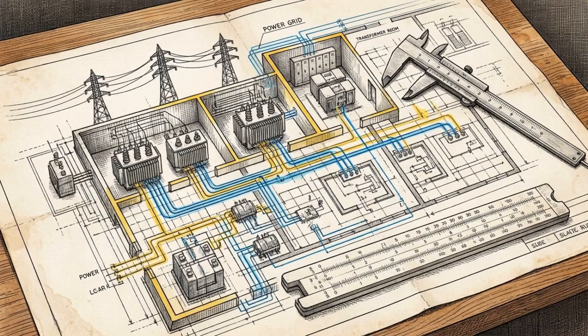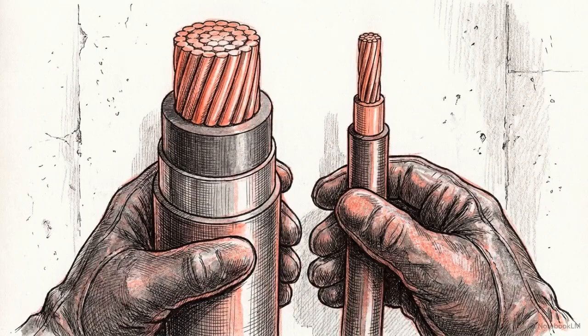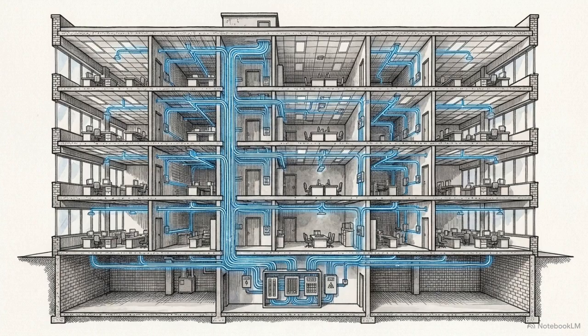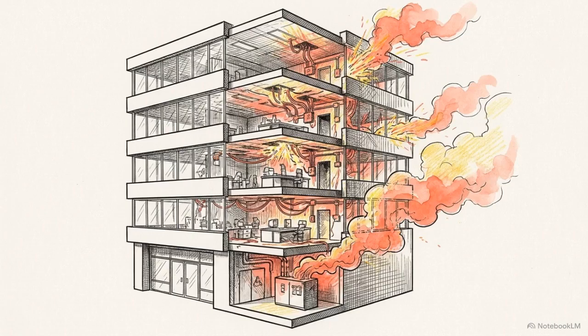For decades, engineers trusted that mathematical perfection. Building codes allowed construction crews to save money by severely downsizing those neutral wires, and they rarely bothered to install circuit breaker protection on them. That means the physical skeleton of nearly every older office building was built on a very specific assumption of perfect electrical balance, an assumption that no longer holds true.